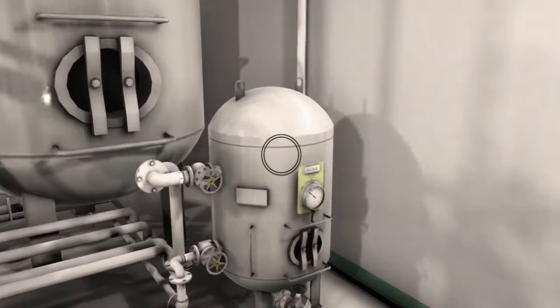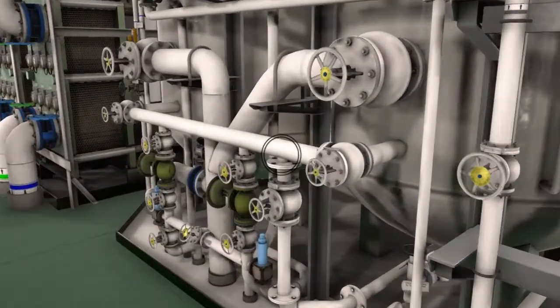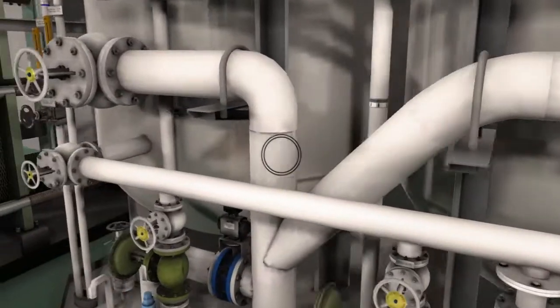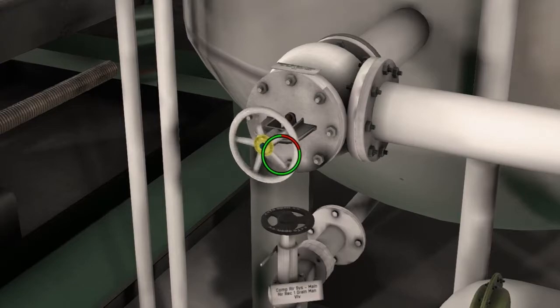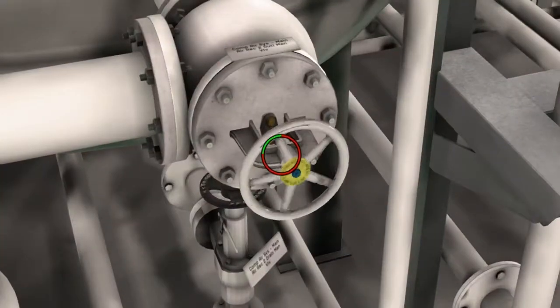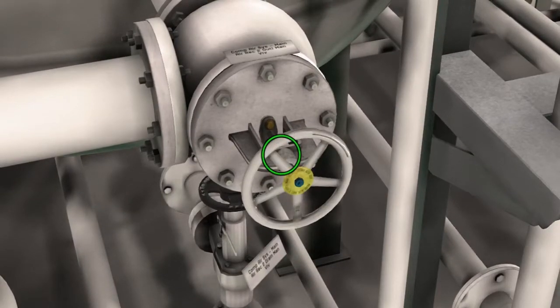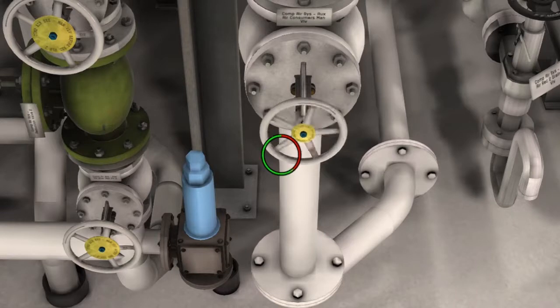When everything is set, we will now line up the service air system. Even though we have an independent service air compressor, this is required since it's connected to the air dryers. Open both main air outlet valves from the receivers, then open the auxiliary air crossover valve. This interconnects the main air to the main air receiver.